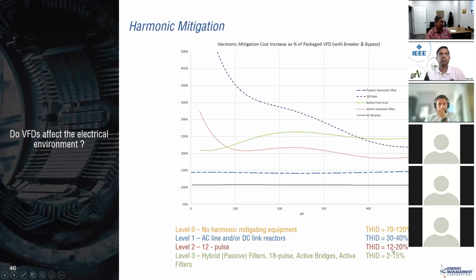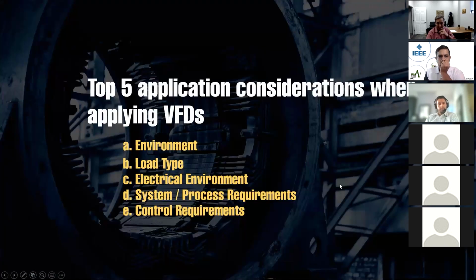IEEE 519, of course, is 5% for the short circuit to load ratio of the larger customer, all the way up to 20%, and the 8 and 12% in between. And then you've got passive hybrid harmonic filters, 18 pulse VFDs, active bridges, and active filters. And as Sid indicated earlier, it's very popular to have these passive harmonic filters, but there are some consequences, like in generators, where you are bringing in power factor with capacitive networks. If you have too much of that, that's going to be a challenge.